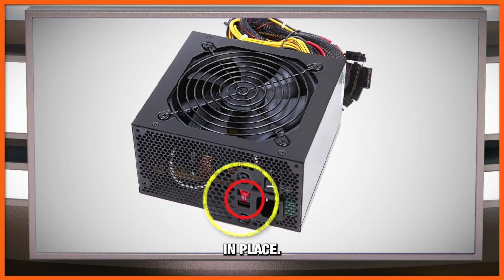Power supplies with these switches commonly ship at 230 volts. The reason is to make sure that if you plug it into 230 volts, you won't get a failure. But if you plug it into 120 volts, the supply might work, but when you load it, it would stop working or not work at all. So make sure that switch is set properly.